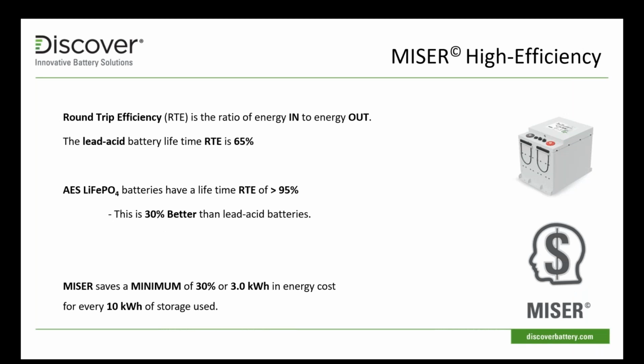Another feature is related to efficiency. We call it MISER. The lithium ion is an extremely energy efficient battery. Its ratio of energy in to out is tops. It's some 98% or thereabouts when it's new, for a lifetime of 95% round trip efficiency. This is some 30% better than your lead acid battery lifetime RTE, which averages out, according to studies, around 65%. That 30% is worth a lot off grid. It means that you're just needing and using less energy and wasting less energy in the process of charging and discharging.